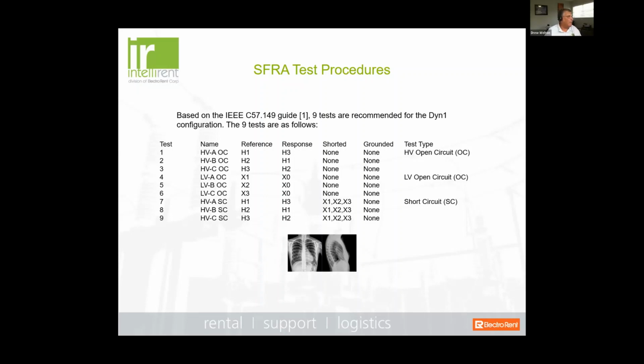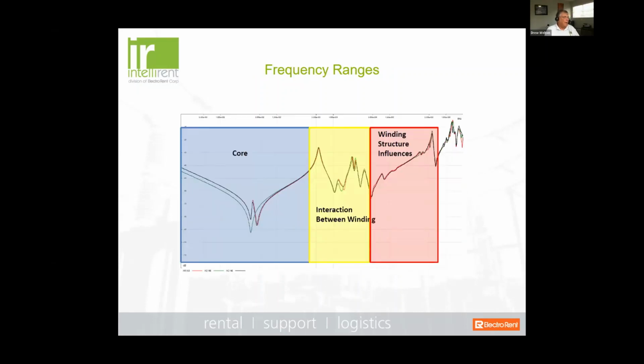And you'll notice here, and again, this is part of the recommended test from C57149, and this is for a delta Y transformer. And of course, this has a 30-degree phase shift between windings. So you have a high voltage, okay, reference H1 to H3, and that's an open circuit test, H2 to H1, H3 to H2, etc. And then your low voltage, X1 to X0, X2 to X0, and this is, again, an open circuit test. So we've got 6 open circuit tests between the primary and the secondary windings, and then we have a short circuit test, okay, on the high side, and then the low side, which you're shorting. Okay, so it's important to go through, whenever you're doing these types of tests, go through the manual carefully, refer to the guide.